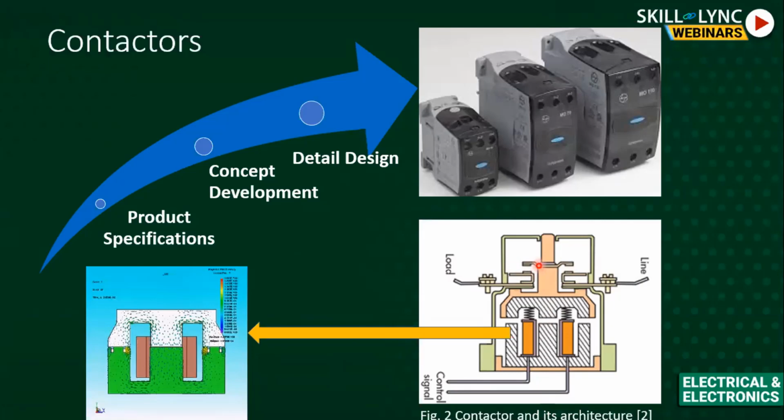So there will be a contact opening at the rated current, which is not intended, because if such behavior is there continuously whenever you are operating this contactor, if there is a reopening of contacts happening, the entire overall life of this contactor will go down, because slowly it will see the arc and it will deteriorate the material on the contact surface. So this is not the best design.